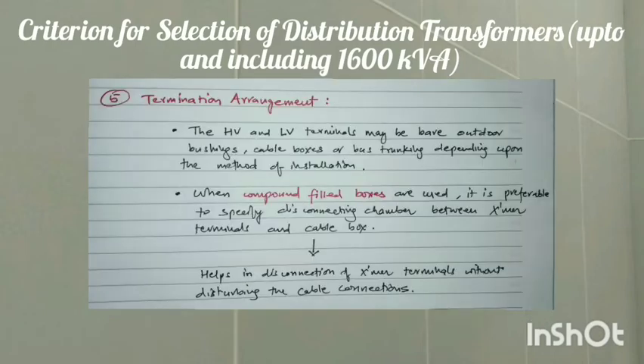Fifth, termination arrangement. The HV and LV terminals may be bare outdoor bushings, cable boxes, or bus trunking depending upon the method of installation. When compound-filled boxes are used, it is preferable to specify a disconnecting chamber. One disconnecting chamber is used between transformer terminals and the cable box. This helps in disconnecting the transformer terminals without disturbing the cable connections.